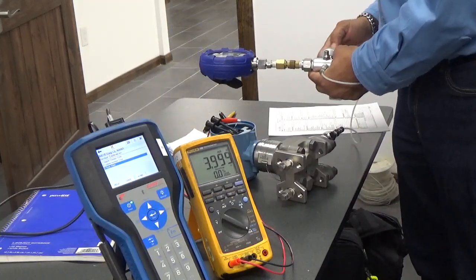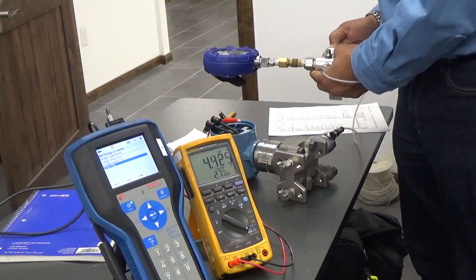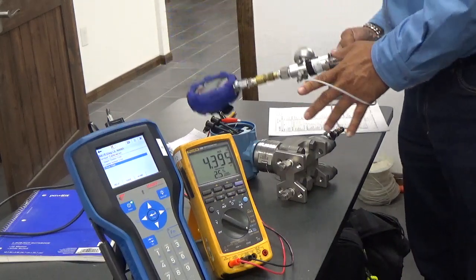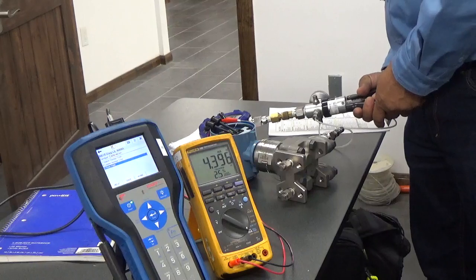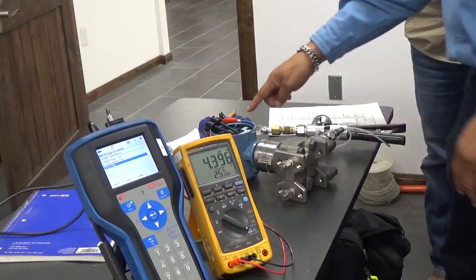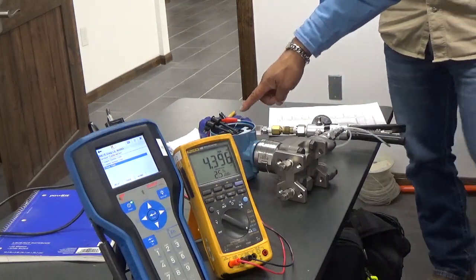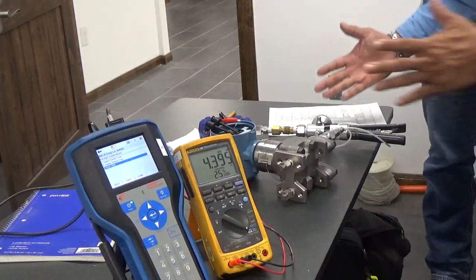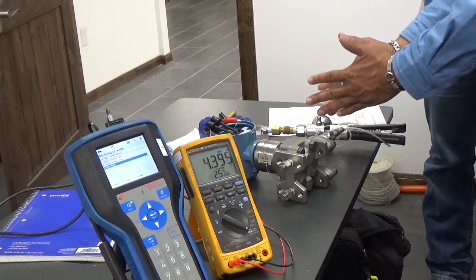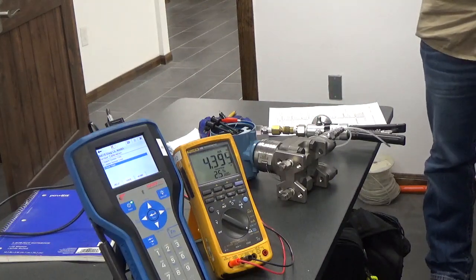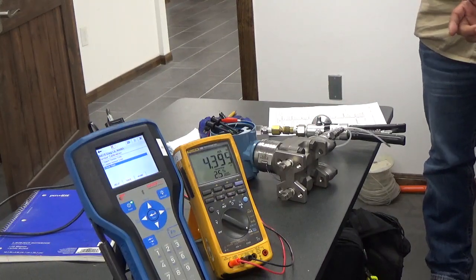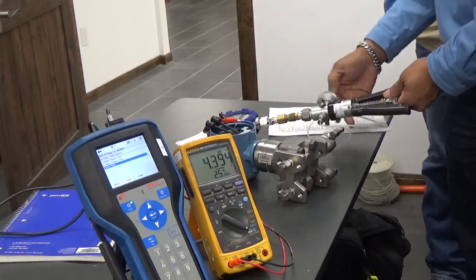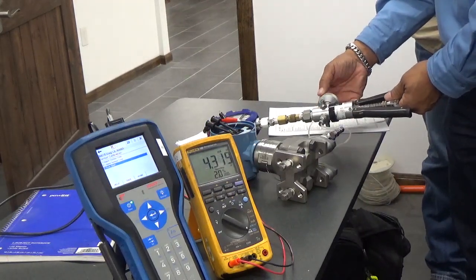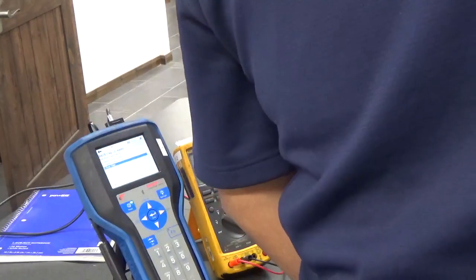So we want to soft seal this right here. We can put a little bit on it, but we don't want to put a gorilla on it. Just by soft sealing it, it gave me 3 inches. That's because inches of water, just the amount of seal it took to press that closed, pressed down to 2.9 inches of water. So I can come right here and dial it back, you see it? Now I'm dialing it back with my fine adjustment.